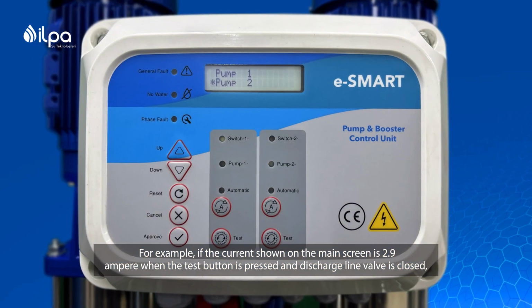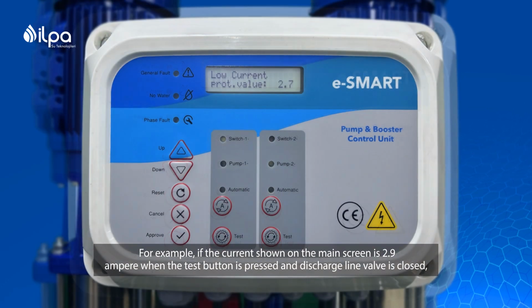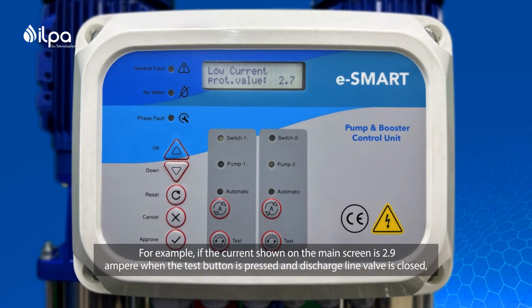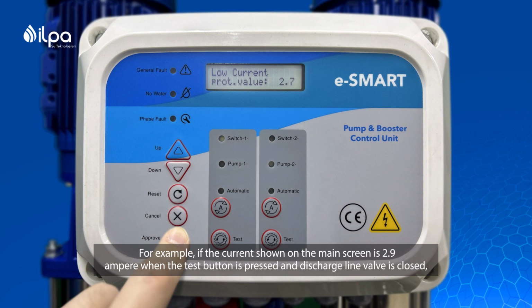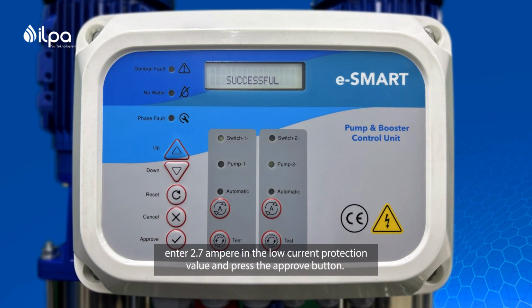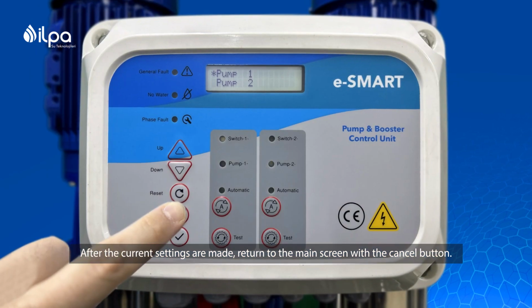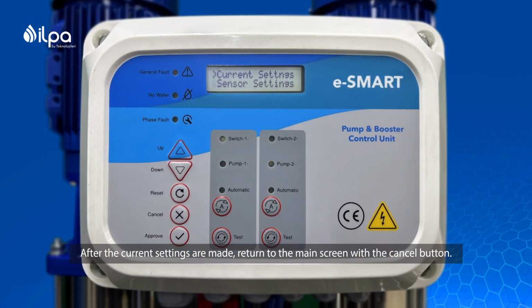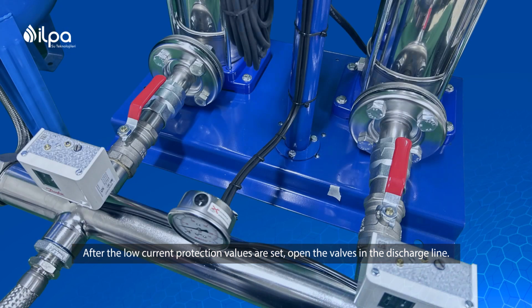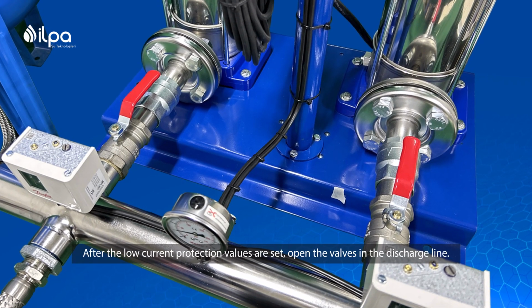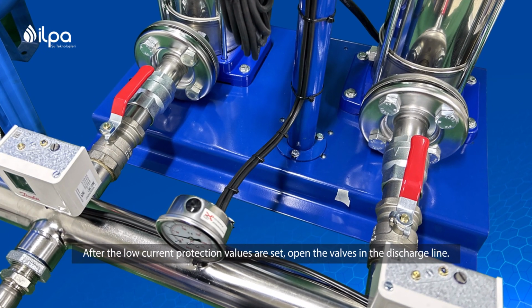For example, if the current shown on the main screen is 2.9 ampere when the test button is pressed and the discharge line valve is closed, enter 2.7 ampere in the low current protection value and press the Approve button. After the current settings are made, return to the main screen with the Cancel button. After the low current protection values are set, open the valves in the discharge line.